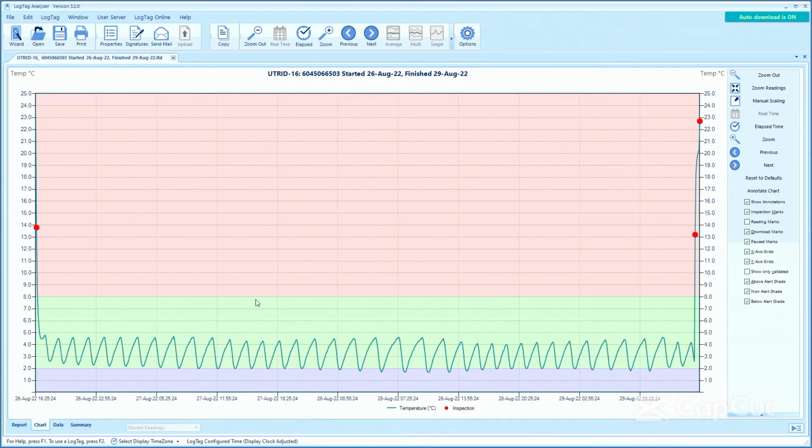And now when we go back to our analyzer, you can see here the current temperatures. You can see that above this 2-degree line, in the green is our between 2 and 8 degree threshold, so everything is good and happy in green. But below, you can see that there's been a few recordings here where it's dipped below. So it's taken readings below our temperature threshold.